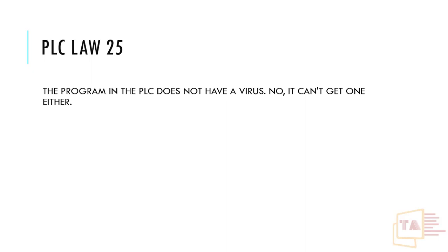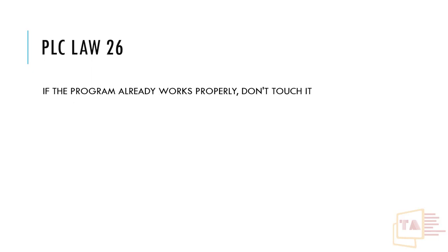The program in the PLC does not have a virus and cannot get one — that is a myth. However, a virus can be transferred to the PC running PLC software via pen drive, photo transfer, data cable, or mobile connection. If you use a PC with PLC programming software and it gets infected, and then you communicate with the PLC, it could be transferred. If you have a PC virus, 100% wipe it clean.